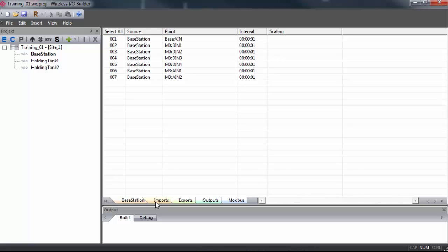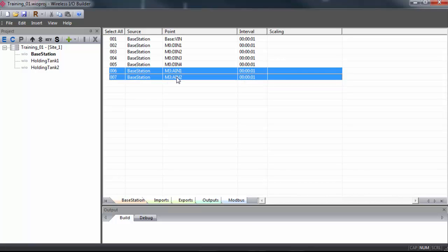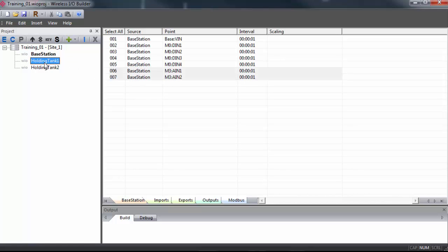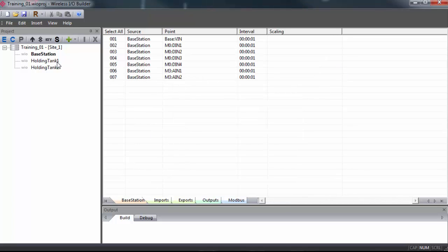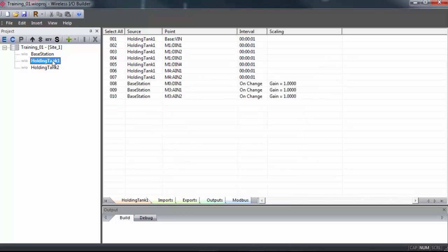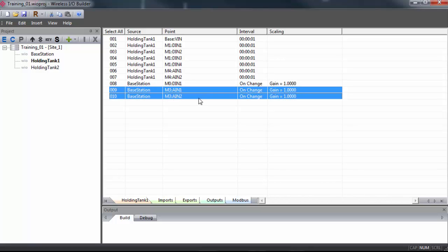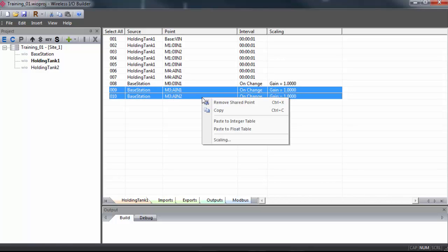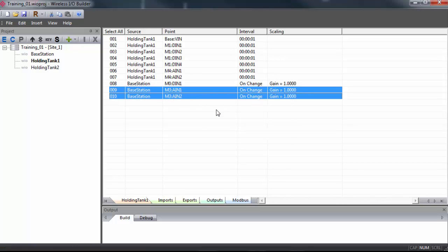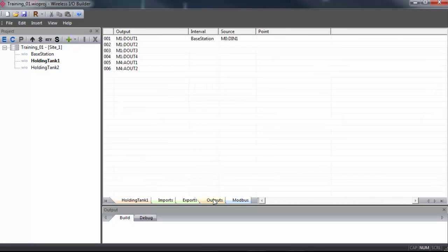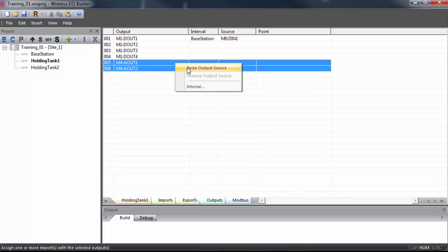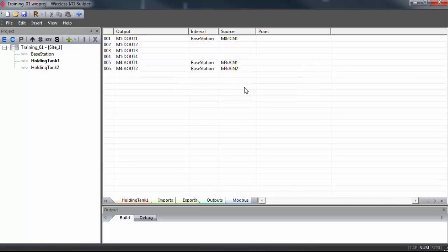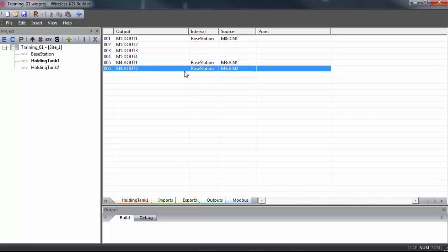With base station selected, I'll go to the imports tab. I'll select module three, analog input one and analog input two. With them both highlighted, click once on the group with the analog module. For me, it's holding tank one and click import. We'll say OK on the confirmation window and we'll select the new points in the imports tab on holding tank one. We'll copy, go to the output tab, and then I'll select module four analog out one and two. And I'll paste. Now, the two analog inputs on base station are driving the two analog outputs on holding tank one.